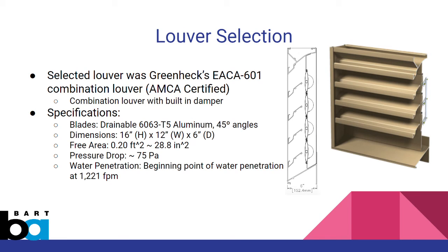The selected louver that we decided would best fit our system is this louver, known as the EACA 601, designed and created by Greenheck. This is a combination louver which has a built-in damper that sits behind the louver's stationary blades. The louver has been tested for its performance and is certified by the Air Movement and Control Association, also known as AMCA, after having been tested through its certified ratings program. It contains drainable blades made of 6063 T5 aluminum, oriented at 45 degrees. The specific chosen dimensions are 16 inches in height by 12 inches in width and 6 inches in depth.